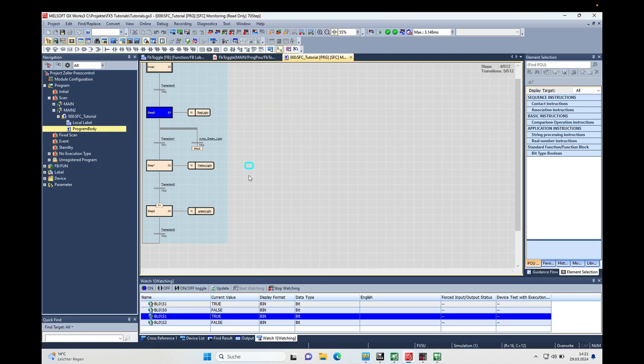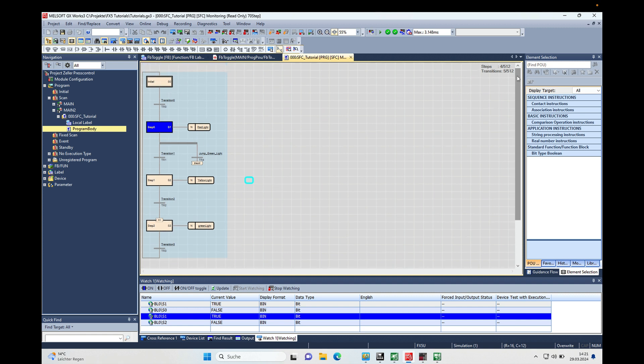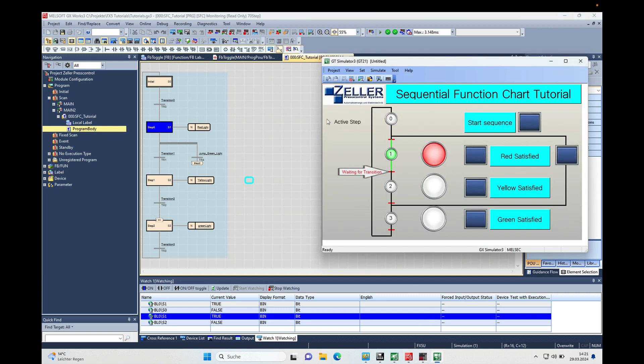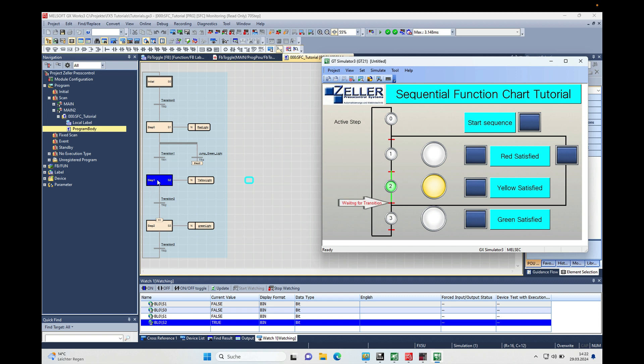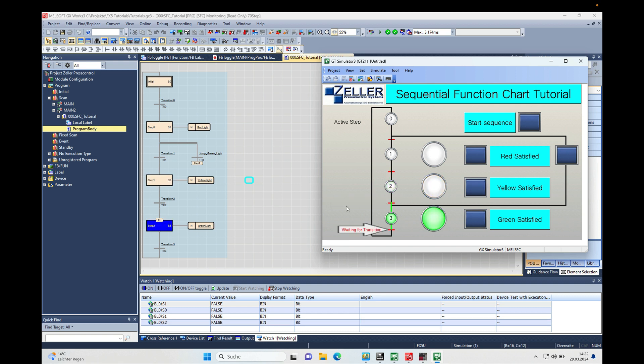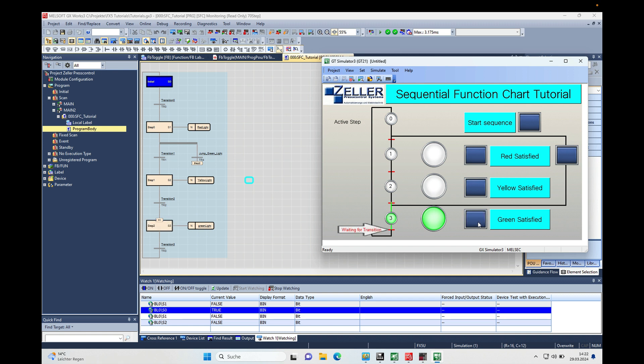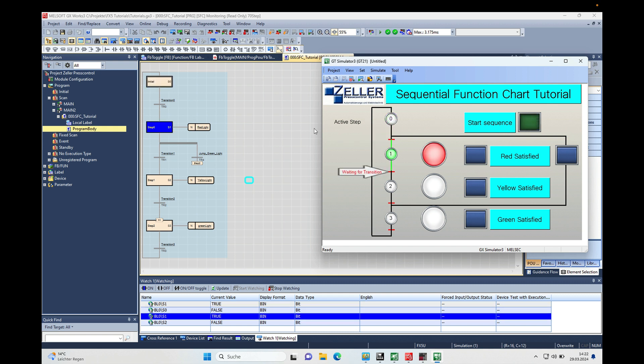In GX Works3 the program looks like this and we can see the individual steps. If I satisfy step number one you will see step number two turn on, and so on. Here you see step number three is active, and if the next transition turns on, this line leads you over to the initial step, which activates the sequence again. Now we are waiting for transition zero — switch this on and the red light turns on.